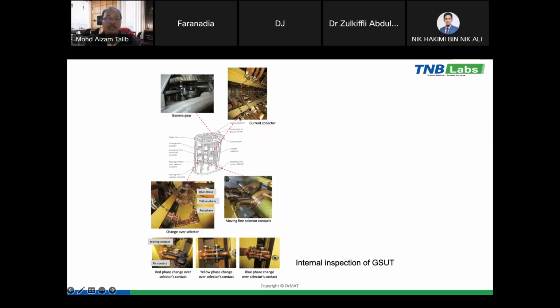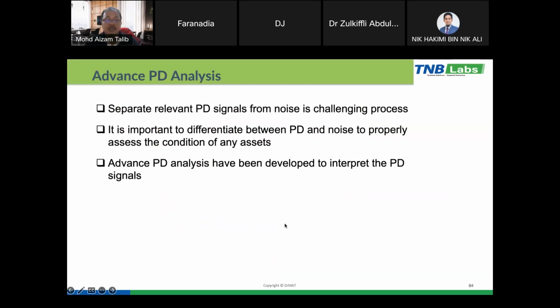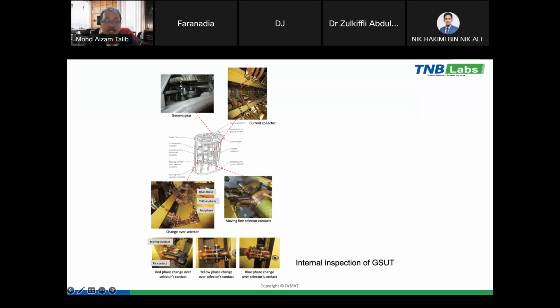And finally, when we open the transformer, we can see there is an arcing sign at the change over selector contacts. Here we can see the red phase change over selector contact has been burned, and the yellow phase shows some sign of overheating. The blue phase is not so bad, but the main defect is on the red phase change over selector contacts.